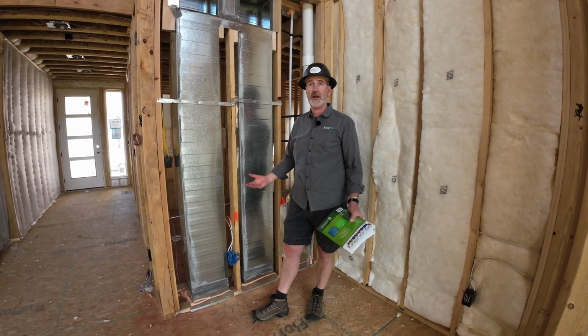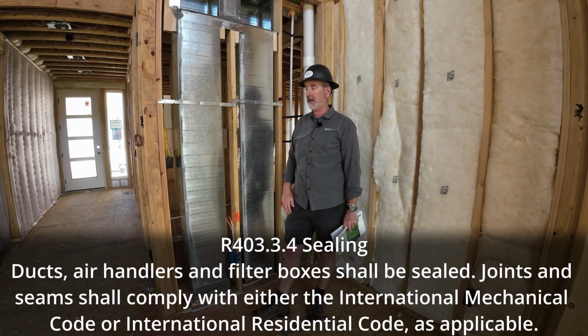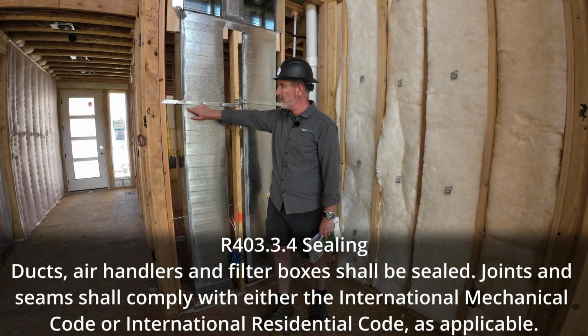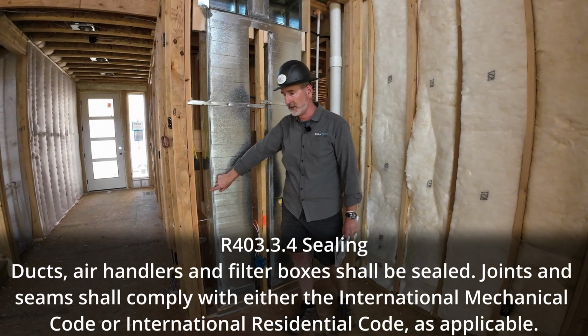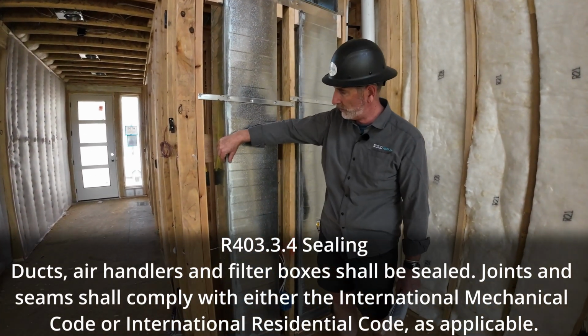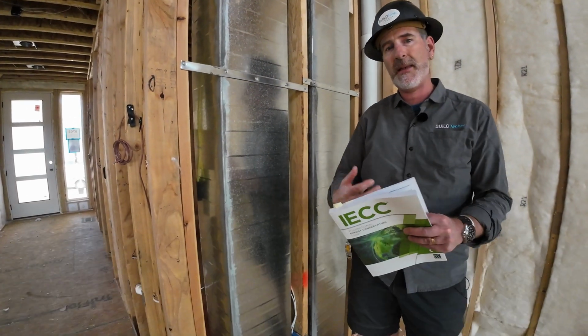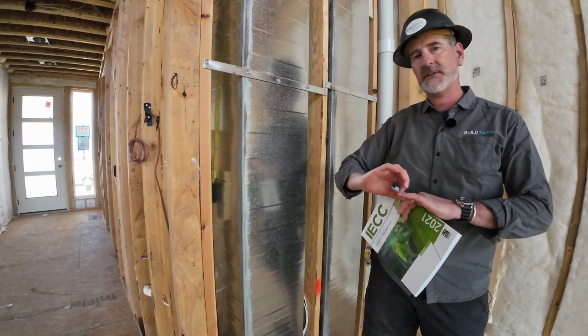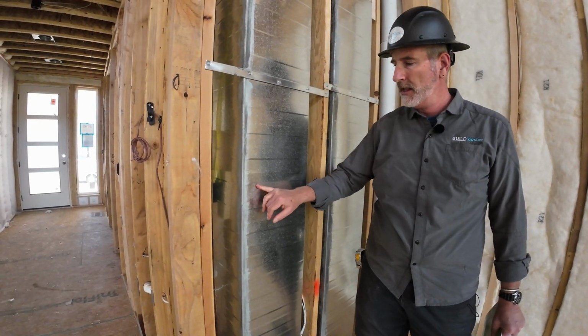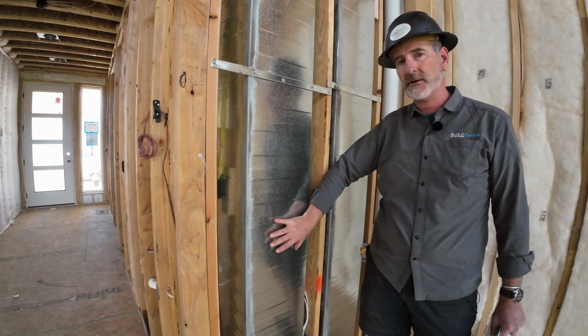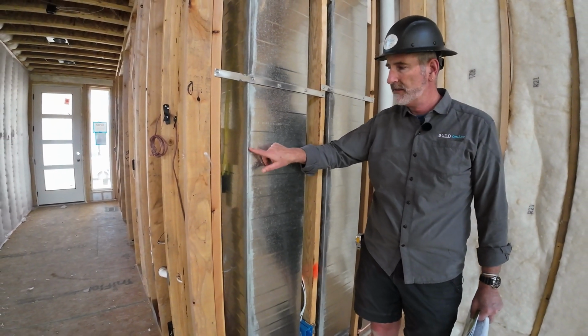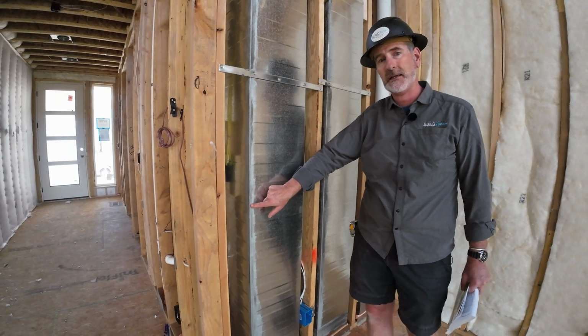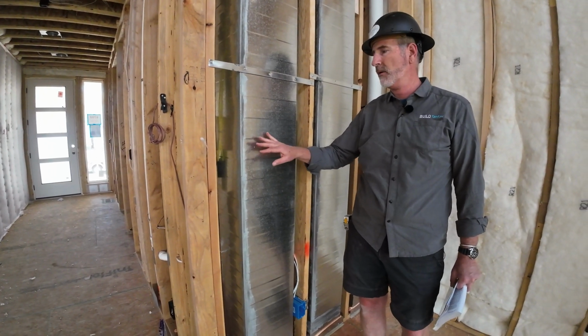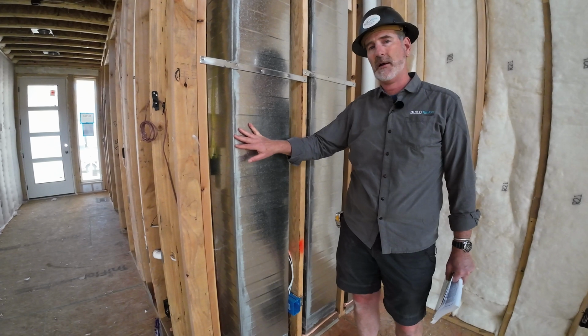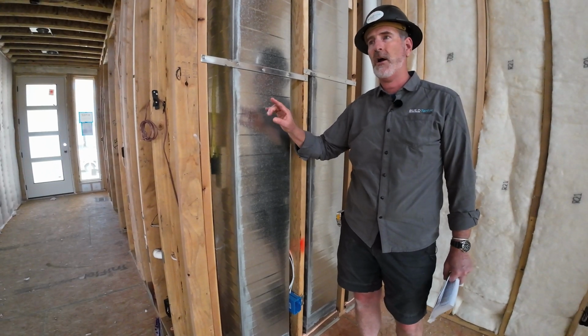We have to do a duct sealing test on a house, and the rough stage of construction is the best time to do it because they've installed the duct, but they've also air sealed this duct. And you can see the mastic coming down what we call a Pittsburgh joint or a manufactured joint, where two pieces of duct actually clip together here. And as these systems get tighter and tighter to meet the requirements of the code, these manufactured joints start leaking. So we want to be sure that we're going to get this mastic product, air sealing product, on all joints of the system.